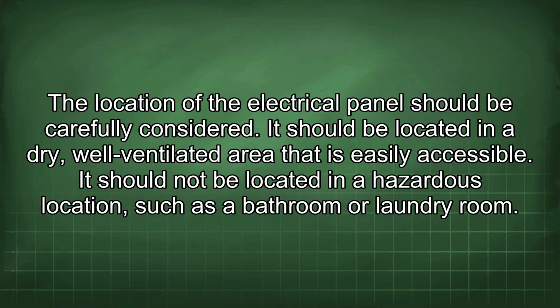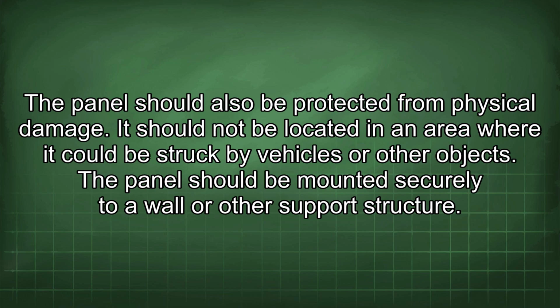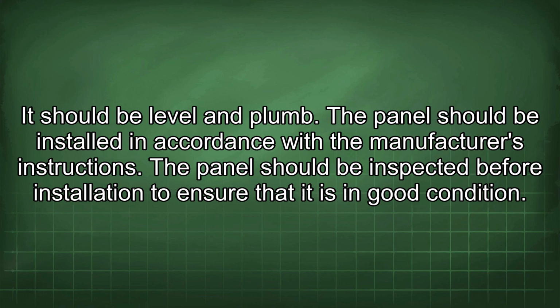The location of the electrical panel should be carefully considered. It should be located in a dry, well-ventilated area that is easily accessible. It should not be located in a hazardous location, such as a bathroom or laundry room. The panel should also be protected from physical damage. It should not be located in an area where it could be struck by vehicles or other objects. The panel should be mounted securely to a wall or other support structure. It should be level and plumb. The panel should be installed in accordance with the manufacturer's instructions.